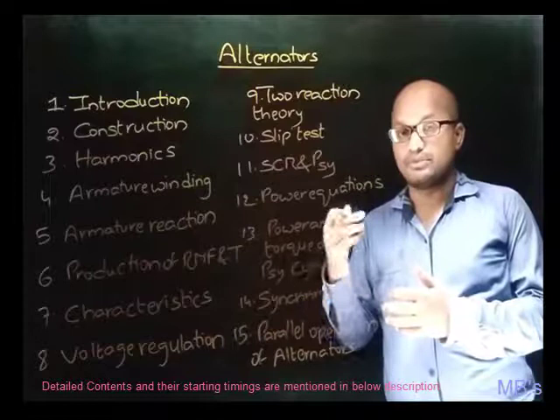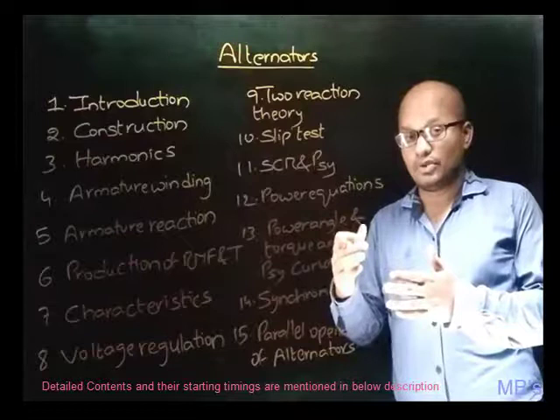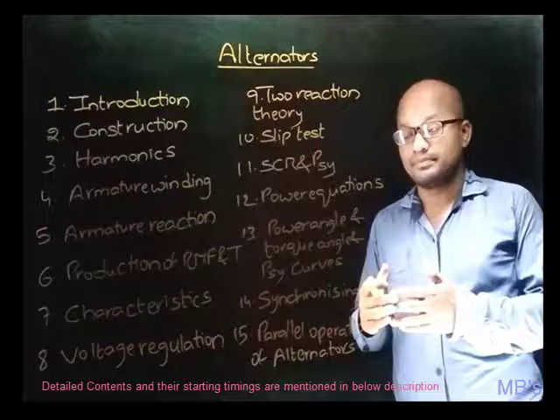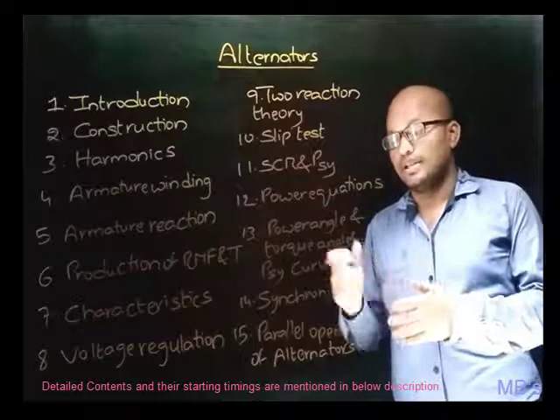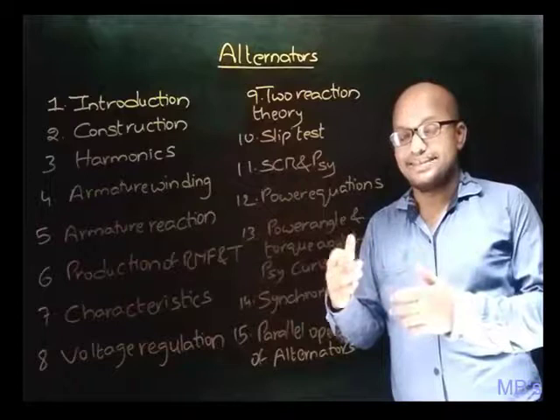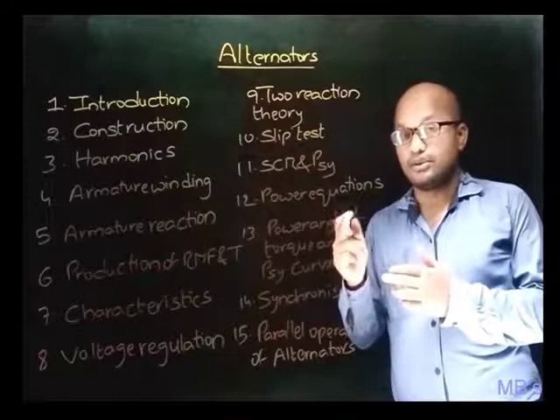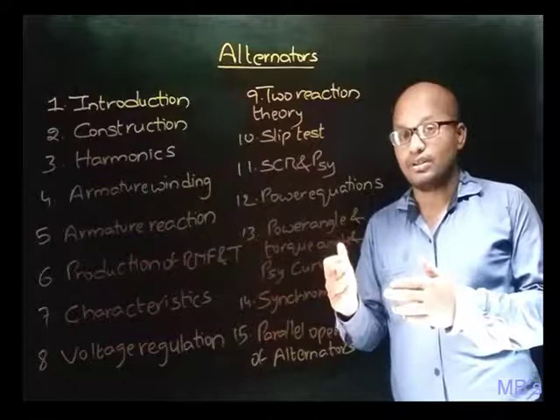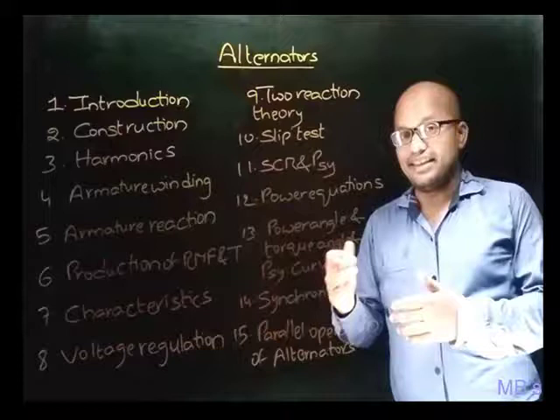This is a beautiful concept which will tell you that by varying the prime mover power input, only active power varies, and by varying excitation, only reactive power varies. This can be better understood from the parallel operation of alternators. Parallel operation of alternators is the most important topic because here what an alternator actually is can be known — cases like two alternators operating in parallel on no-load and loaded conditions, and when an alternator is connected to an infinite bus under no-load and loaded conditions, along with important curves like V-curves and inverted V-curves.